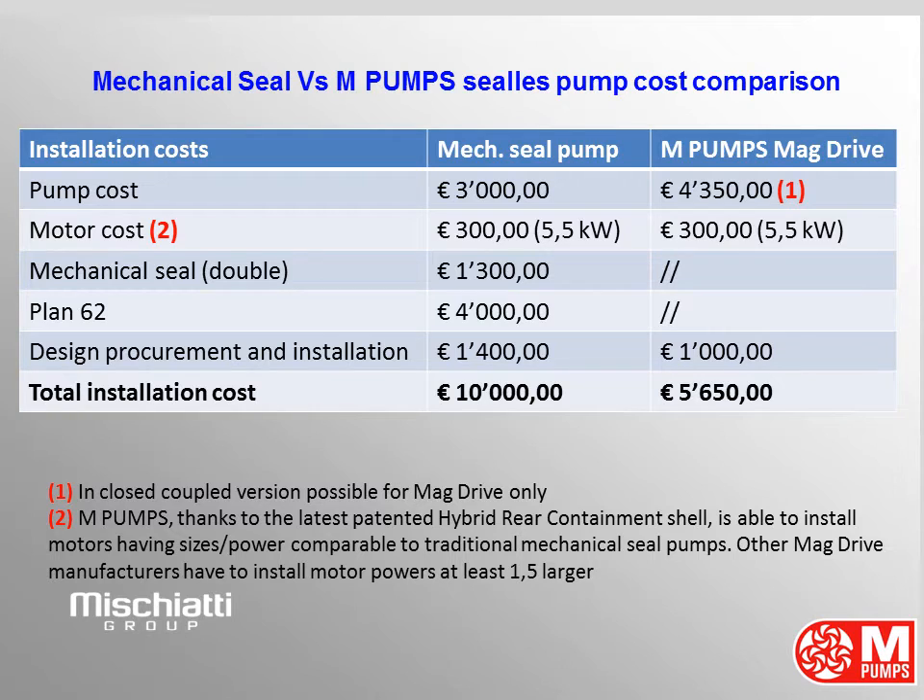Other mag drive manufacturers have to install motor powers at least 1.5 times larger than M-Pumps. Motor cost is 300 euros for a 5.5 kilowatt motor for each pump. Double mechanical seal costs 1,300 euros; magnetic drive pumps have no mechanical seal, so no cost for it. Plan 62 costs 4,000 euros and is mandatory for double mechanical seal pumps; magnetic drive pumps do not need Plan 62, so no cost again.